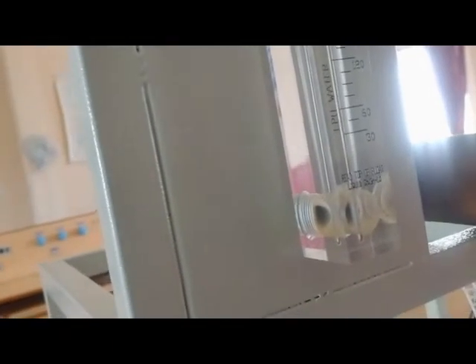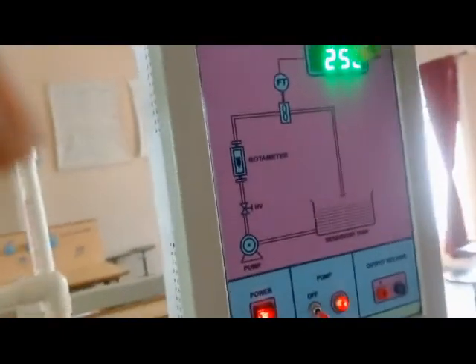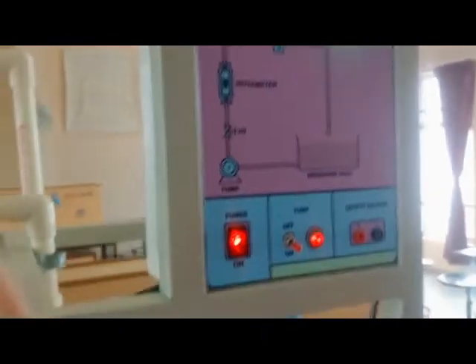Adjust the gate valve so that the rotometer value reads 240 LPH — that is, liters per hour. You can now see the display reading from the sensor is 245.